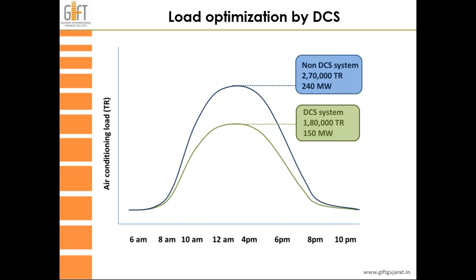So we are also using a TS tank with our plant — a thermal energy storage tank that takes care of the peak loads between 12 p.m. and 4 p.m. It gets charged during off-peak hours and discharged during peak hours. So I don't need a chiller capacity of 180,000 tons; it can be lower, around 75% of the peak load. Our combination for GIFT City is 150,000 tons of chillers and 30,000 tons from TS tanks, for 4 hours. So roughly we need around 120,000 ton-hours of TS tank capacity for the entire city cooling.